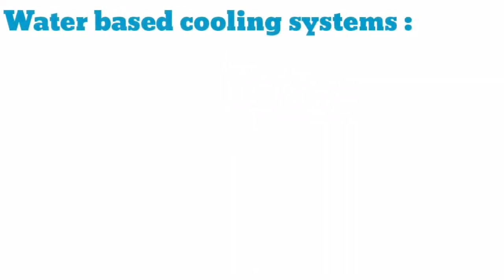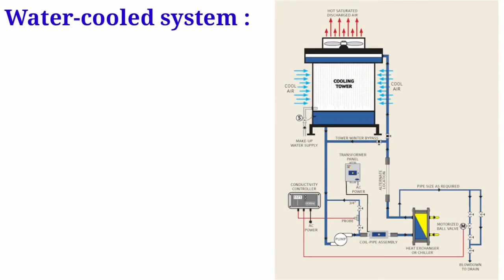Three types of HVAC systems utilize water in the cooling process. The first type is water-cooled systems. These systems reject heat from the refrigerant to water in a water-cooled condenser. Typically water enters the condenser at 80°F and leaves at 90°F. The water then goes to a cooling tower where a portion evaporates, and the remaining water with makeup water is circulated back to the condensers. Where water is scarce, dry coolers are used instead of cooling towers to prevent water loss.